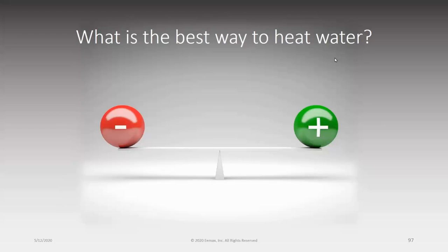Can you give some examples of different hot water heating systems that would comply with the limit of 2 to 3 feet from the heating source? So for the IPC code, it states that you have to be within 2 fluid ounces from your heated source to the termination of the fixture. The heated source is generally going to be a water heater, a recirculation loop, or a heat trace temperature maintenance system. So if you use a tankless water heater underneath the fixture, you have the ability to be right at that point. You could be within 6 inches.